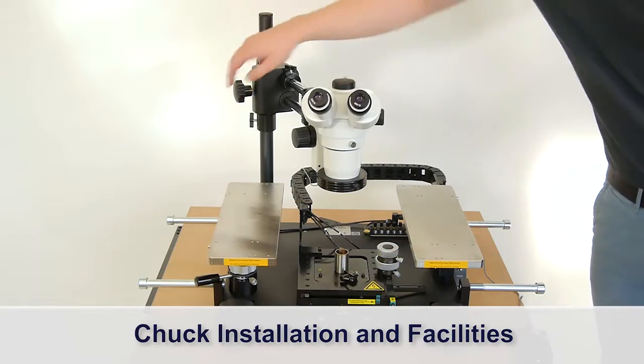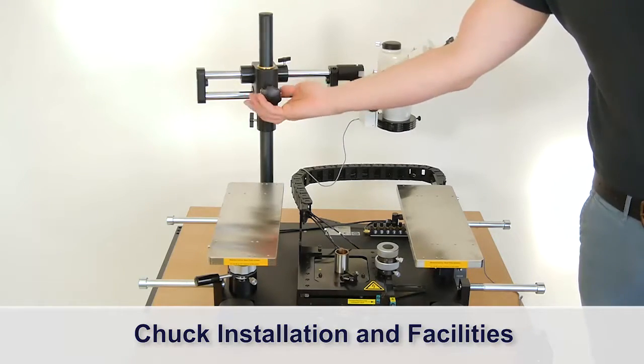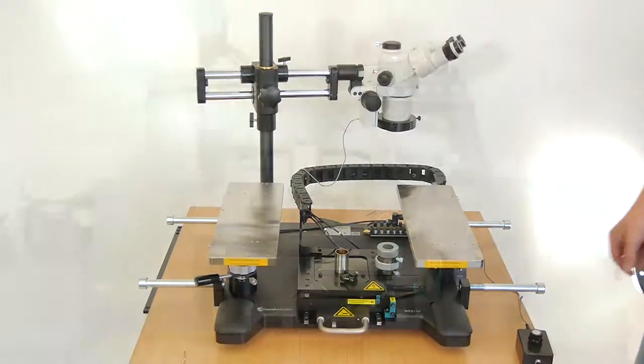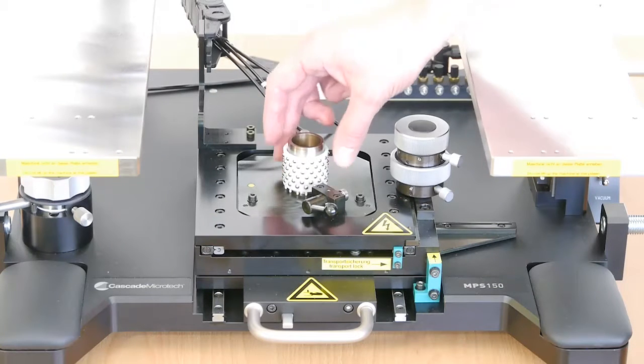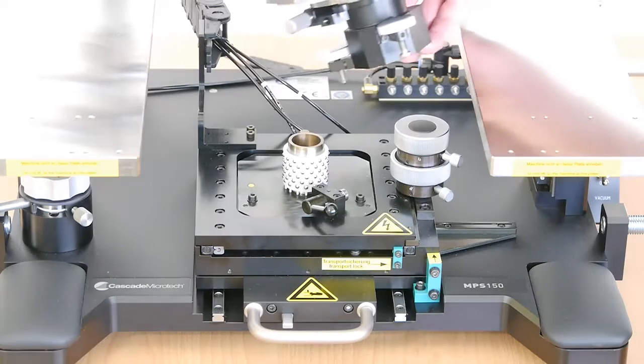For getting access to the chuck stage, turn the crossarm to the side. Take the ball bearing cage and put it over the chuck stage post. Now you can insert the chuck assembly.